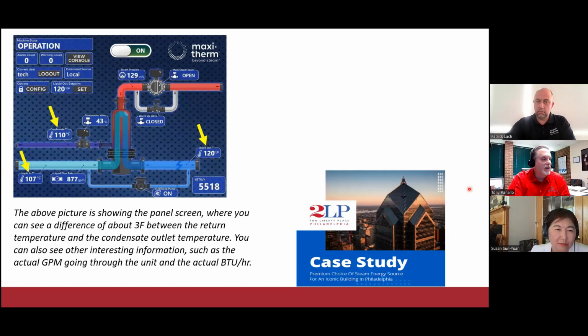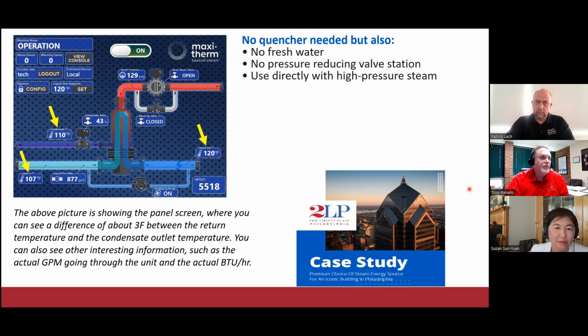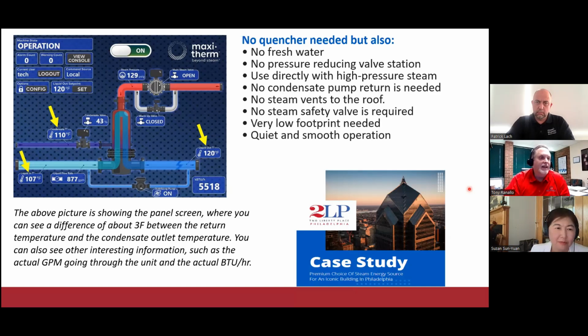One of the things I'd like to point out is this particular case study. This is 2 Liberty Place in Philadelphia. This is a building that was electric, and they were looking at how to save energy, so they decided to go to natural gas. The district loop operator at the time, which was Veolia, now Vicinity, runs that loop. And they convinced them that they should not go with natural gas, but to go with steam.